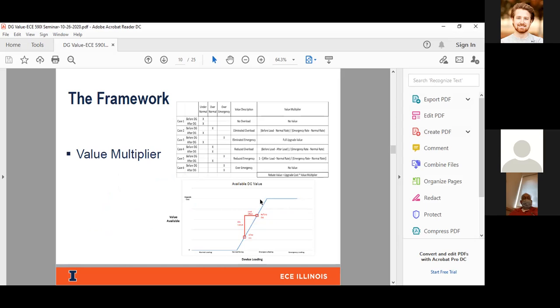In here, we have a quick matrix that I put together that really walks through what we call the rebate value multiplier. And it's a way to capture that value that a DG could provide a specific asset. Back to the planning criteria, we said anything under normal operating limit is really okay. It's not a violation of the planning criteria, so the utility is not going to initiate any projects for it. So there's really no value for DG that is located downstream of an asset that is not seeing any violations or any problems.